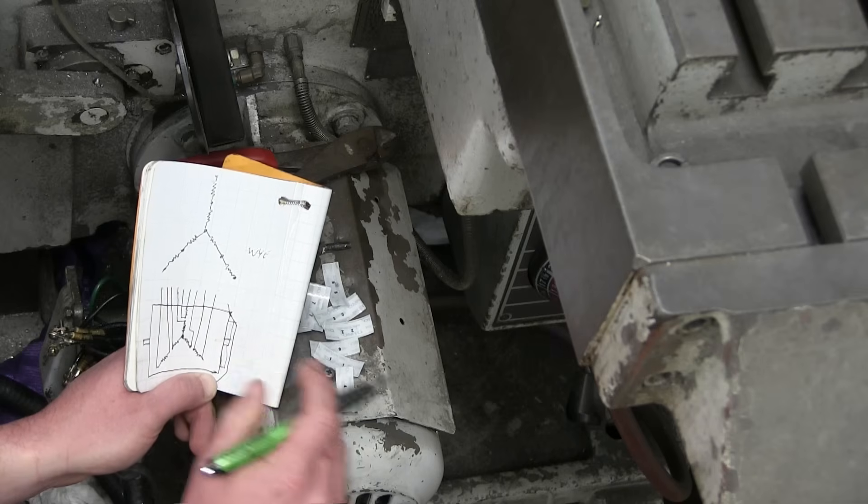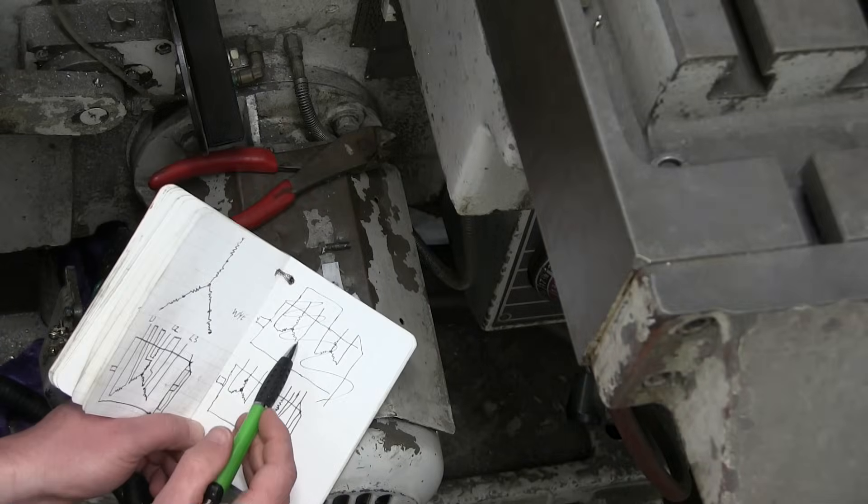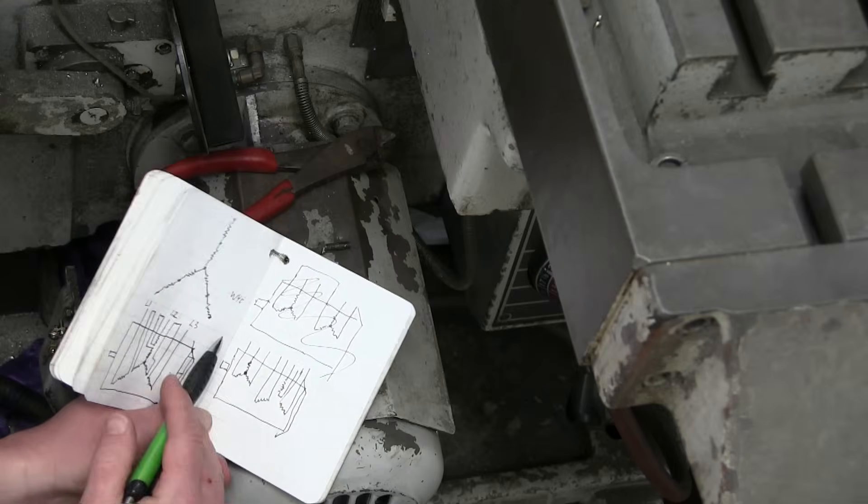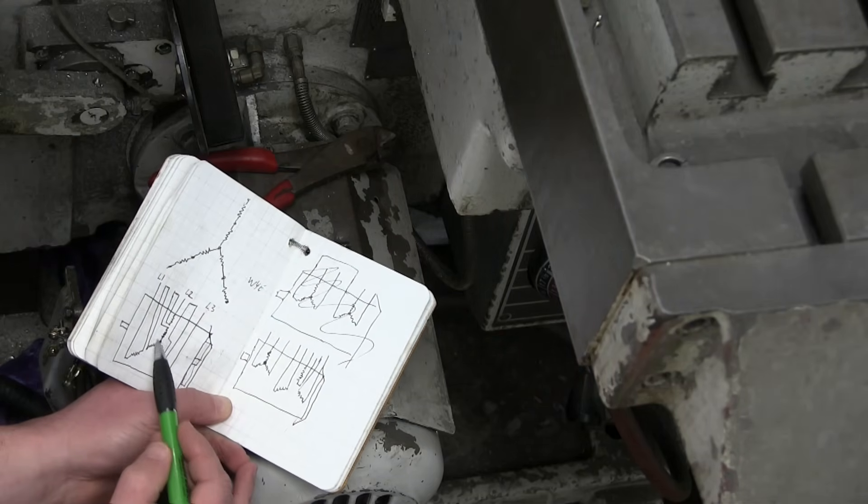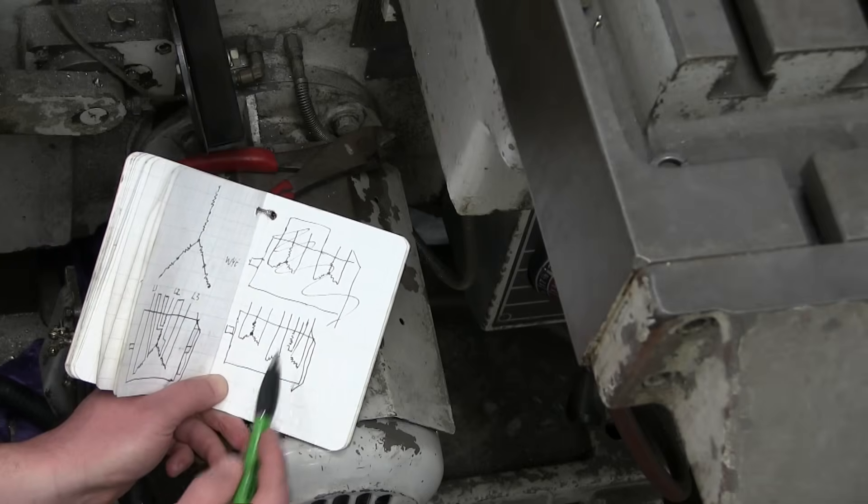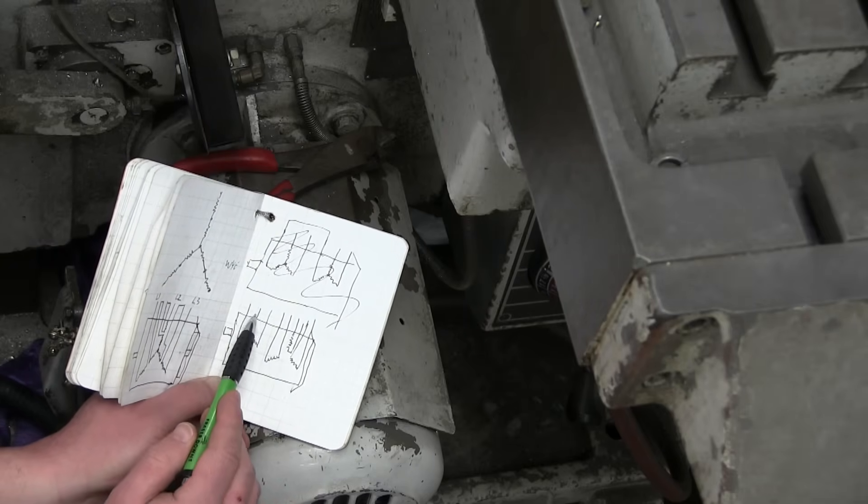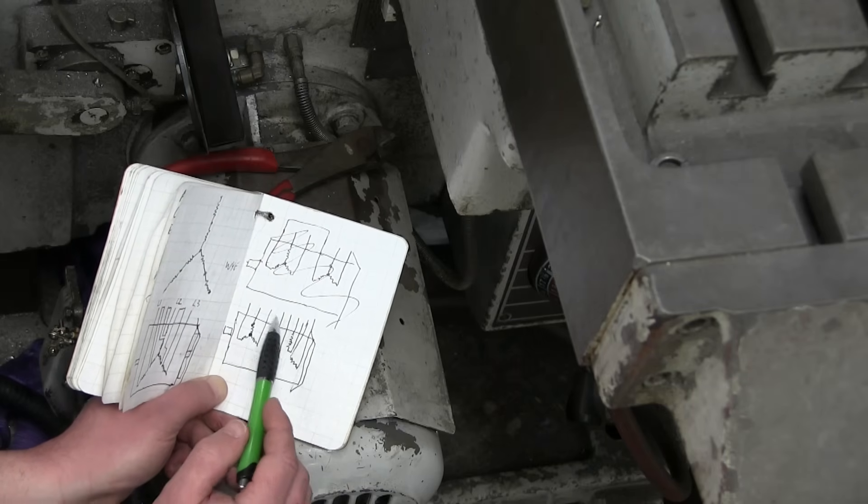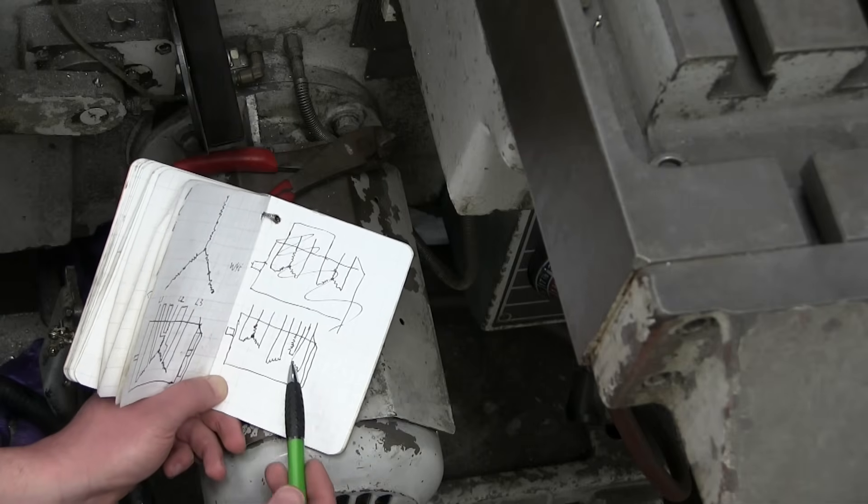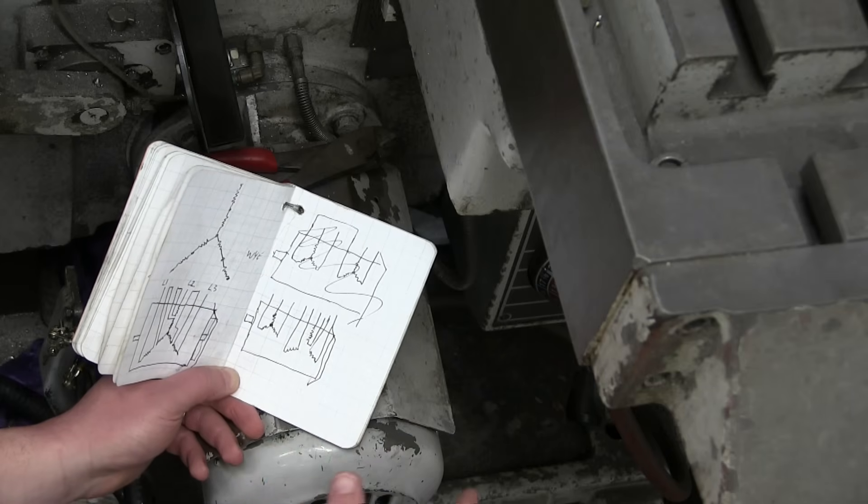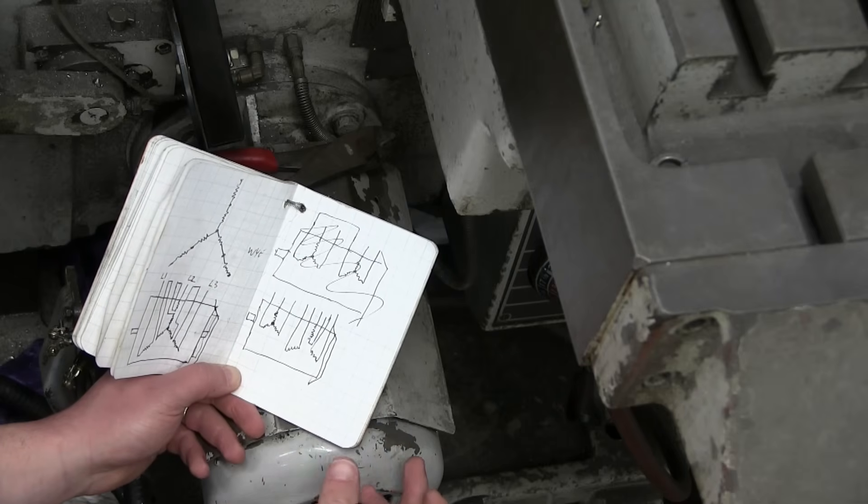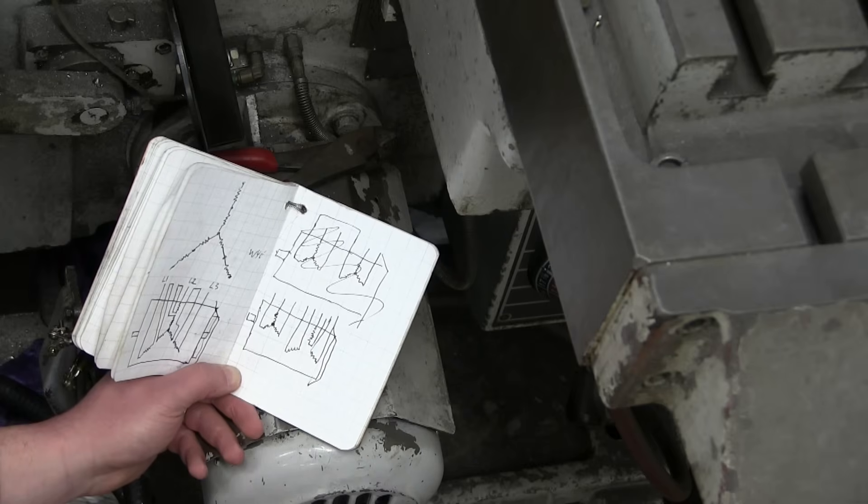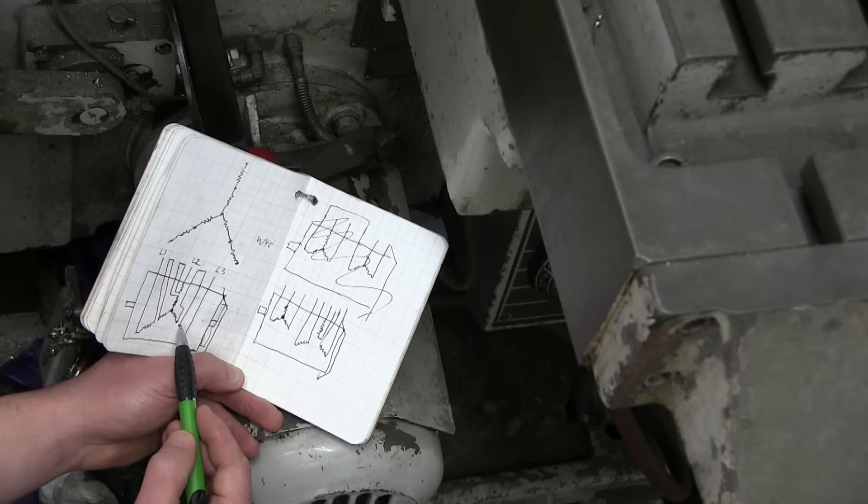Now if we want to go lower voltage, what we need to do is we need to parallel these. So instead of the one Y, we're going to take this Y and we're going to double it using these outside windings. How do we do that? Well, we just wire up the connections different. So instead of the one Y, what we get is two separate Ys. I'll make a drawing. Here's where it gets a little tricky, as witnessed by my stumble at the start. Remember, we got nine wires coming out of this motor. So the center part still has the tap internal, we don't get to see that, but all these outside windings all have the wires coming out. So all we need is there's three wires from this tap, but we need the six wires from this Y, and that gives us of course nine wires.